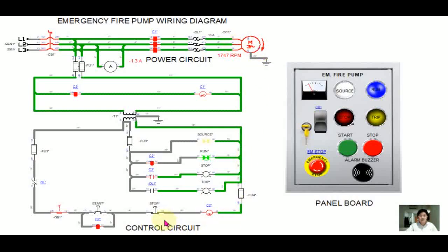I can also stop here. The lights are also indicated run. The contactors are closed, as you can see. So I will stop here. The motor stops. You can see the indication here in the ammeter stop. There is an illumination here of the stop light indicator, as well as here. So we know that this circuit is working properly, as I simulated here. You see that this is working properly.